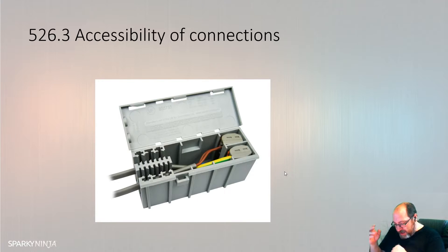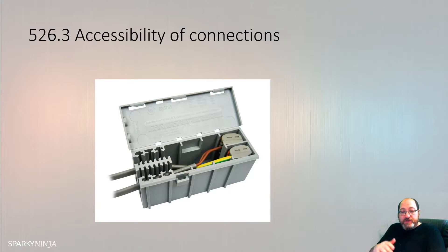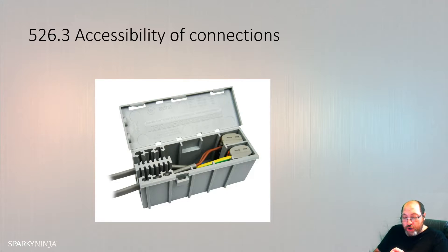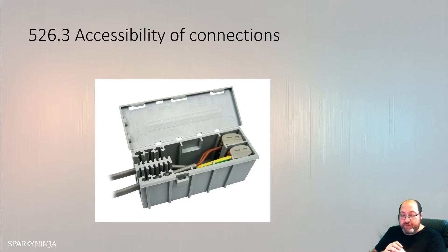526.3 tells us every connection will be accessible unless it's a joint designed to be buried in the ground, a compound-filled or encapsulated joint, a connection between the cold tail heating element, a joint made by welding, soldering, brazing, or appropriate compression — such as a crimper, which would be an appropriate compression method — or joints or connections made by the manufacturer of the product, such as simple push-fit contacts.